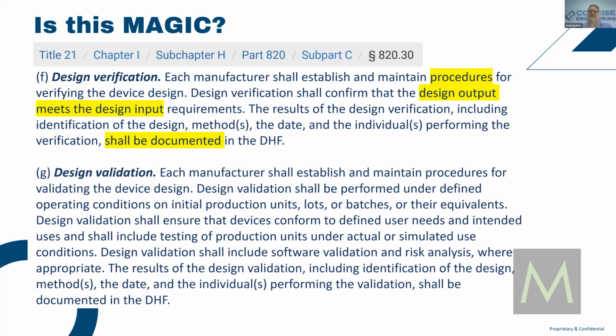And then in design validation, the same types of things come through. You still have to have procedures. You still need to document all your evidence. And now they talk a little bit about the fact that you need to have users, simulated use conditions, and be in this production equivalent zone. So you can't take an early stage prototype, do design validation, and say that you're done. You can do that, take credit for it, and then repeat it later as you get nearer and nearer to the end. But you don't want to ever assume that something you did on that early stage prototype is going to fly for design validation.